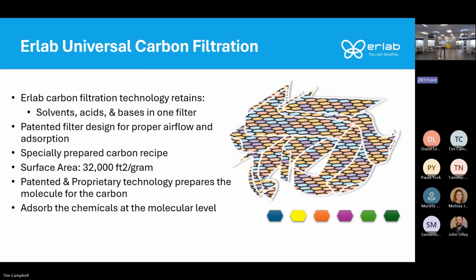Think of popcorn. Before you pop it, you have those smooth kernels with not a lot of surface area. Once you heat it or activate it like we do with the carbon, that kernel pops open and you have all those nooks and crannies inside, and that gives more retention space or retention capacity to the carbon. And what we do is we adsorb at the molecular level. Also, our filter design is very important to have a nice even distribution of carbon through the filter, so there's no leaks, no preferential pathways, because air will find the path of least resistance. So you want nice even airflow through the filter.